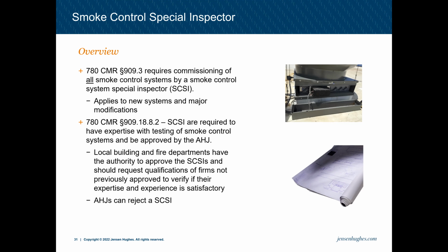In Boston, we tend to see a lot more requests for this. Usually it's coming from the fire captains, but those people tend to be asking for the special inspection if you're doing, sometimes even, a new smoke control panel or a new fire alarm system. They will require this to be inspected. And that's not only inspection for the work being done, but that the system, not just a fire alarm system, is working and interfacing with smoke control correctly, but also that the system is working the way it's supposed to work. And we'll talk about that with a semi-annual test in a little bit.